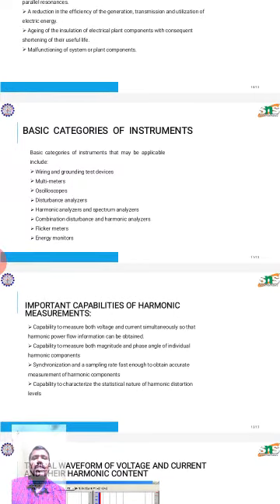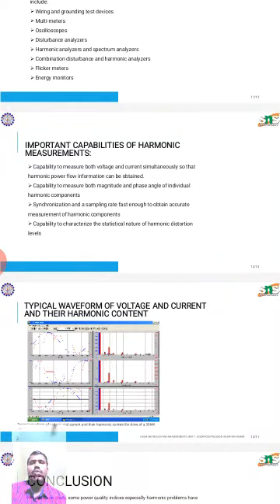Next one, important capabilities for useful harmonic measurements. The important capabilities for useful harmonic measurements are, first one, capability to measure both voltage and current simultaneously so that harmonic power flow information can be obtained. Next one, capability to measure both magnitude and phase angle of individual harmonic components. Third one, synchronization and a sampling rate fast enough to obtain accurate measurement of harmonic components. Fourth one, capability to characterize the statistical nature of harmonic distortion levels. These were some four categories.